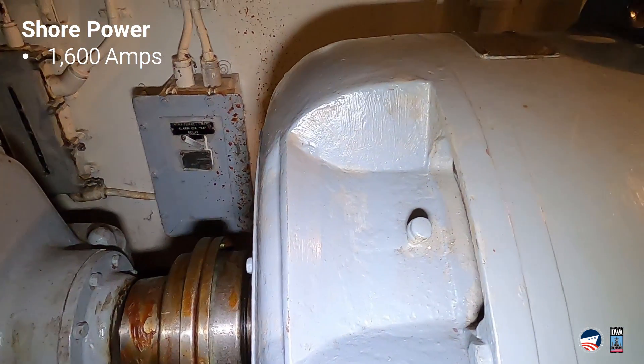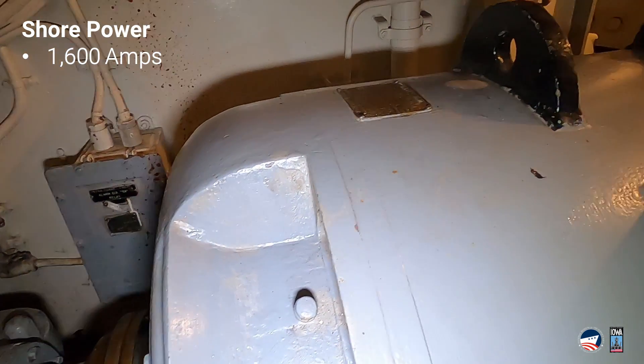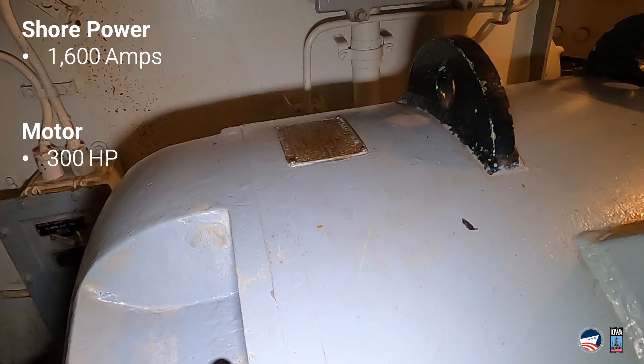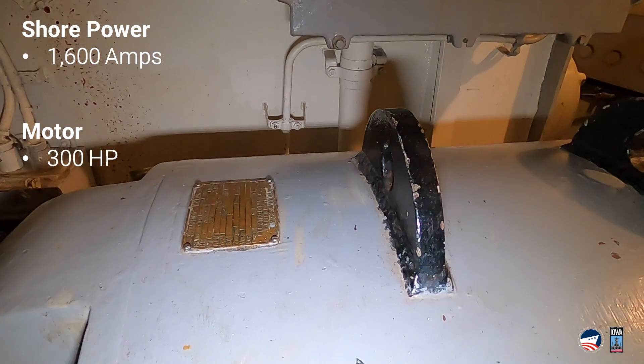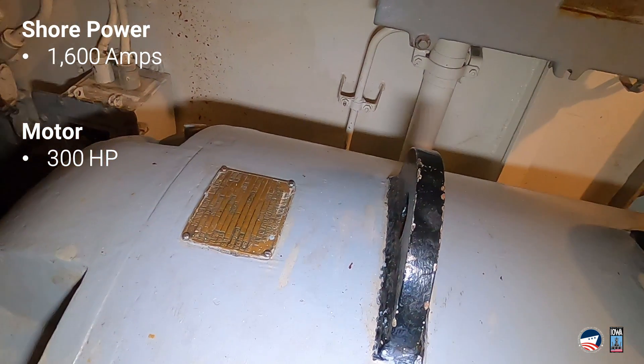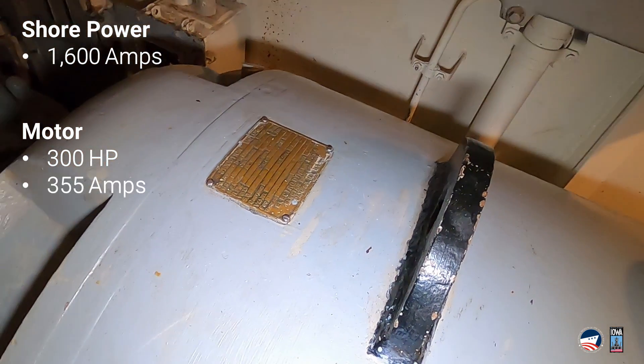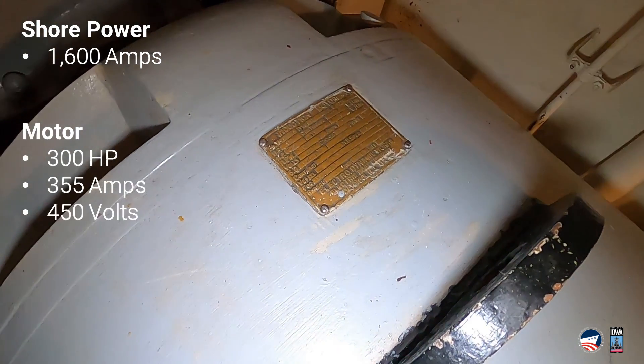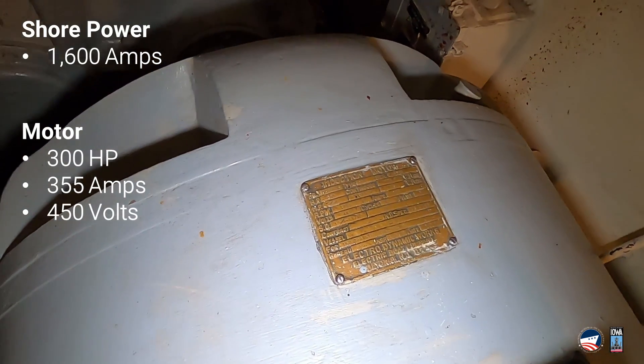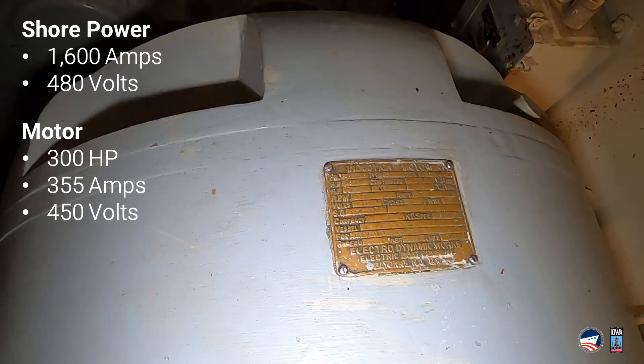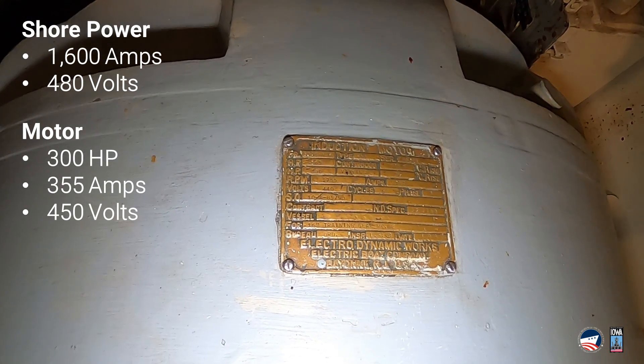1,600 amps is what we have coming into the facility. Now, the motor itself is pretty big. It's the largest motor on the ship. It's 300 horsepower. It draws 355 amps at 450 volts. We're actually running 480 volts here just because the utility provides that.